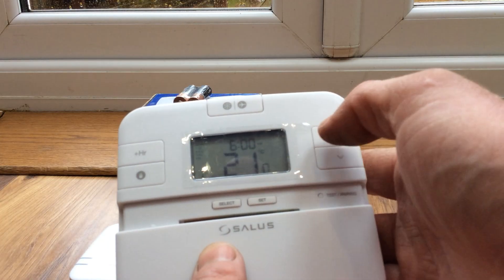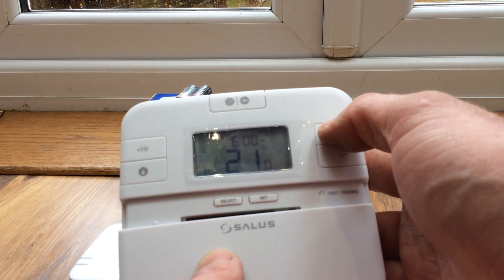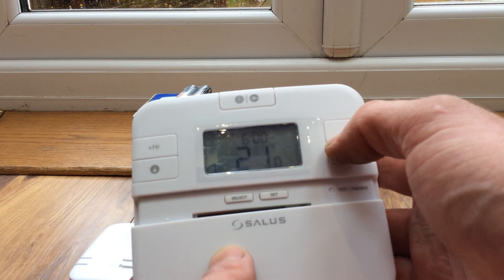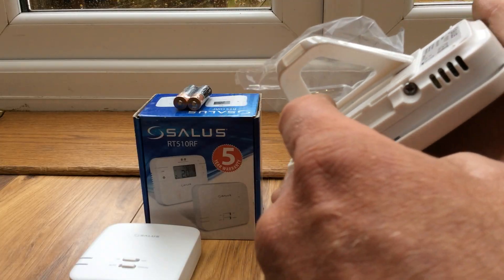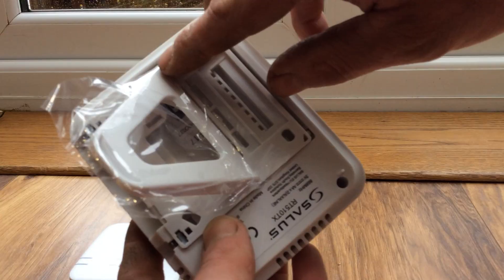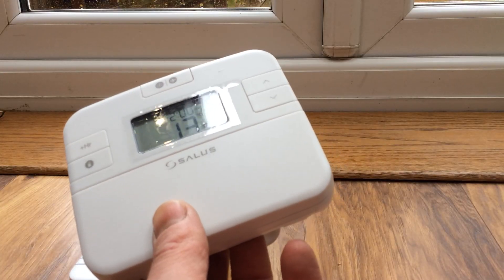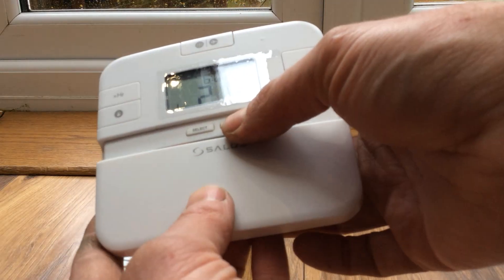Can you see that — the days are flashing. To change the value of the thing that's flashing, use your up and down arrows. Your options are Monday to Friday, or Saturday to Sunday — there's no other options by default. So you have to set Monday to Friday and then Saturday to Sunday separately. You can't do seven days unless there are dip switches under there that you can change to get seven days, but be careful — you might get seven individual days.